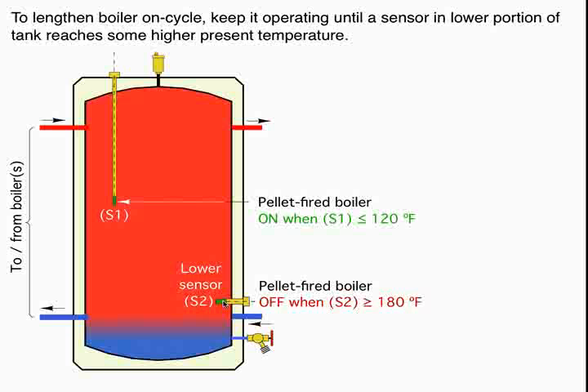Now, we've installed another temperature sensor near the bottom of the tank. It doesn't have to be right at the bottom. It could be one of the lower sidewall connections on a Thermocon tank. But notice what our off condition is here. Our off condition is when that sensor reaches 180 degrees Fahrenheit. So that's a wide temperature swing on the tank. And what this does is it prolongs the operating duration of the pellet boiler on cycle, and that improves efficiency, and it also reduces the emissions coming from it.